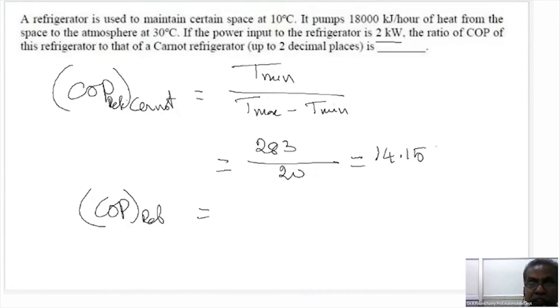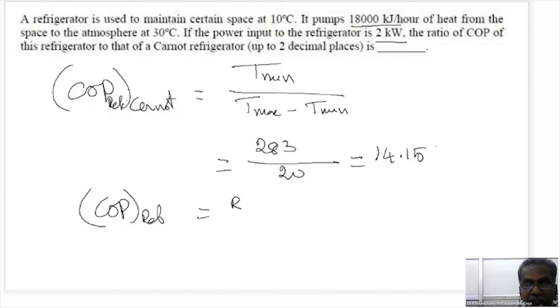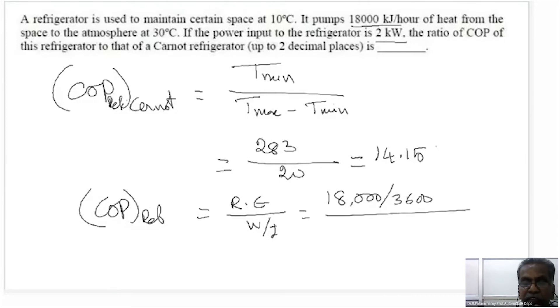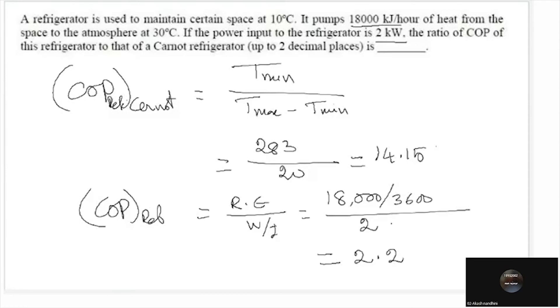Power consumed is 2 kilowatt. It pumps 18,000 kilojoules per hour from the space to the atmosphere. COP of the actual refrigerator equals refrigerating effect divided by work input. That is 18,000 divided by 3600 kilojoules per second, divided by work input of 2 kilowatt, giving 2.5.